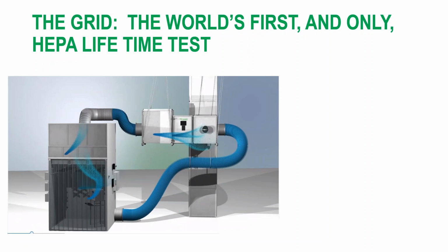This is the world's first and only HEPA lifetime test, performed in a facility in New Jersey in the US. The goal of this test was to validate several different manufacturers' HEPAs, all under the same conditions, across glass, PTFE, and the so-called EnerGuard media, and see how they all stack up.